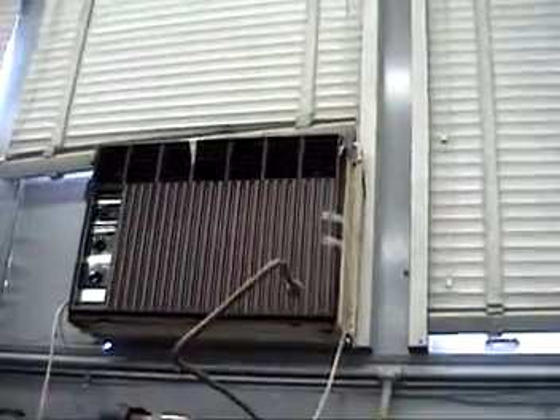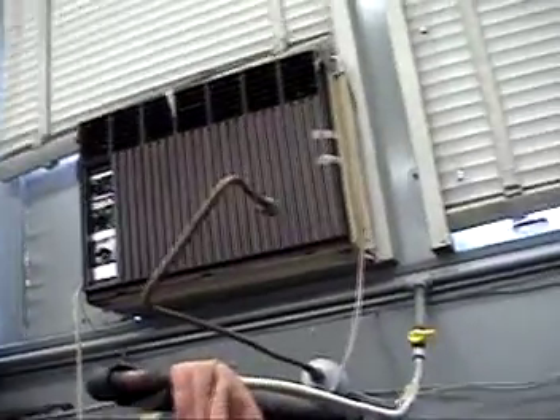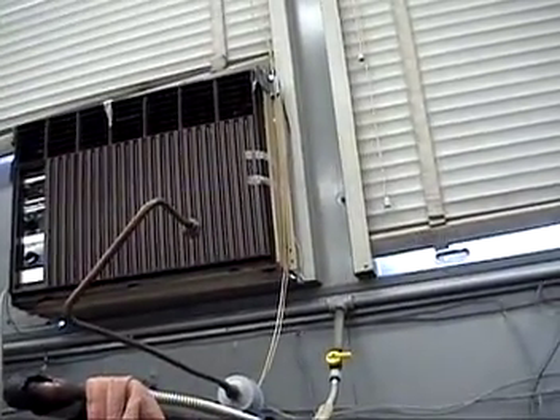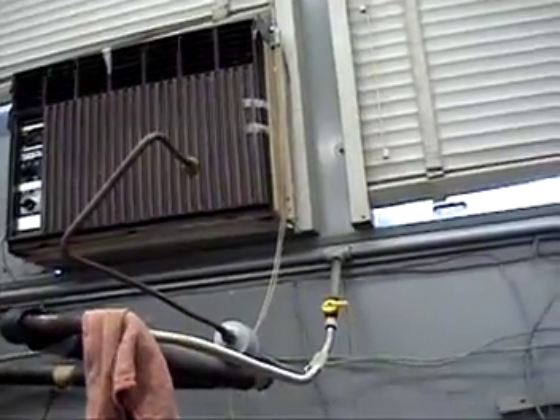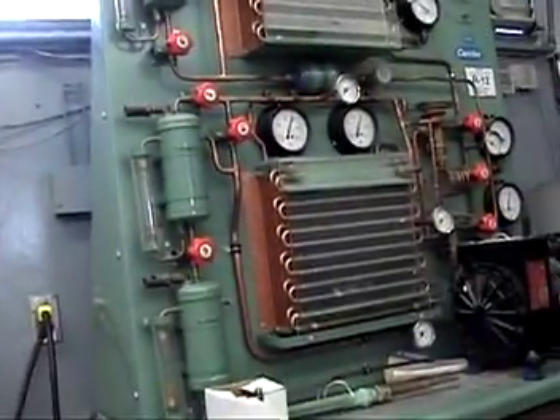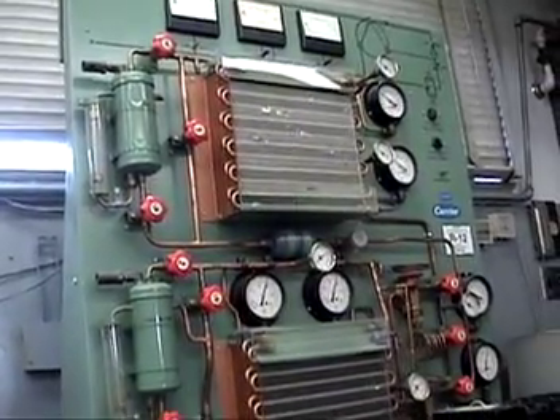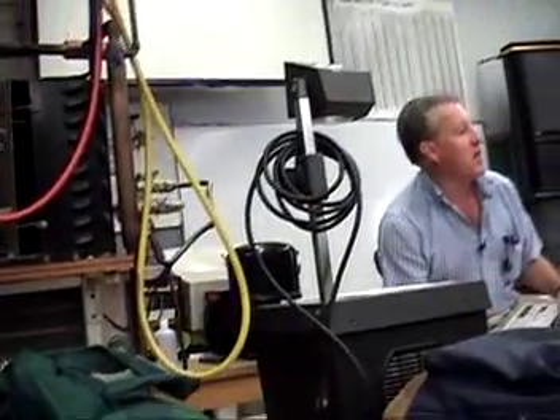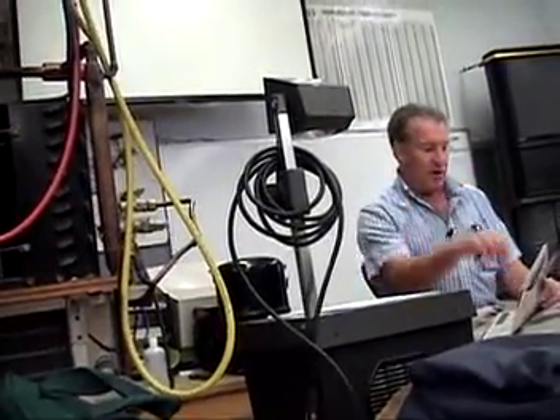Now, those don't come with line taps. You got to put your own line tap in there. There's no place to put a gauge on, so you put your own line tap so you can put your gauge on. Those don't come with it like a regular air conditioner. They're all sealed at the factory. Let's say you wanted to see if there was any freon in it, or if it was reversing, or what the pressure was. You'd have to take a line tap, like a piercing valve. Yes, sir, and you'd have to pierce right into it so that you'd be able to put your gauge on.